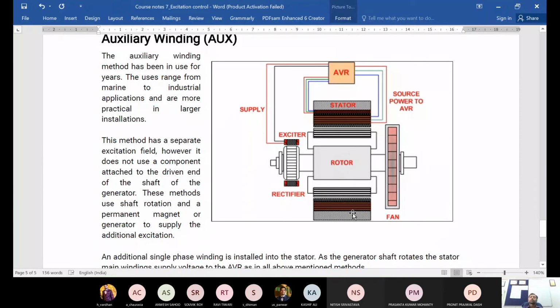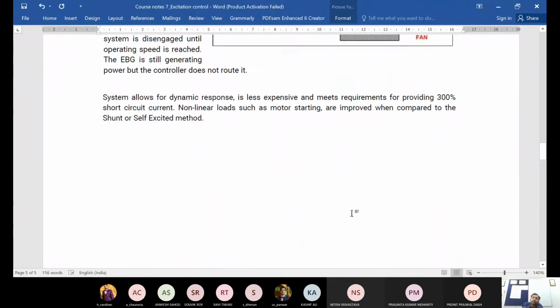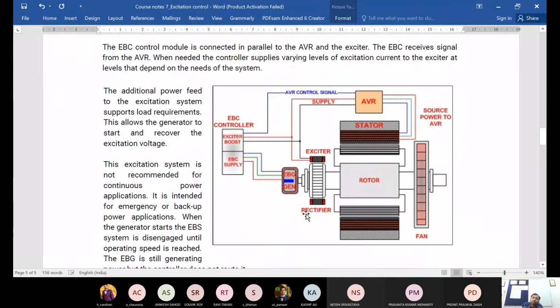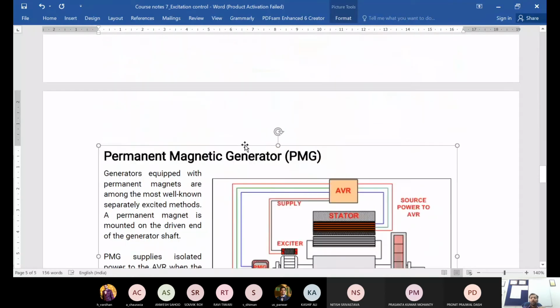One is the complexity, another is the performance, two parameters. In terms of complexity, this is the most complex one, and will provide the best performance because you have an additional controller and it's properly controlling the generator output of this EBG. So this will be the most complex one, but obviously performance is also best, though slightly higher on the cost side as well, and complexity as well.